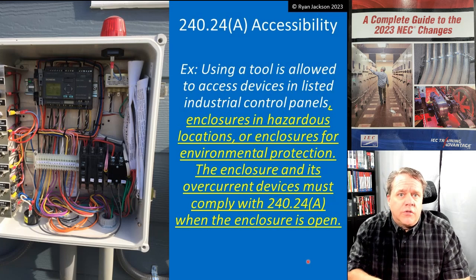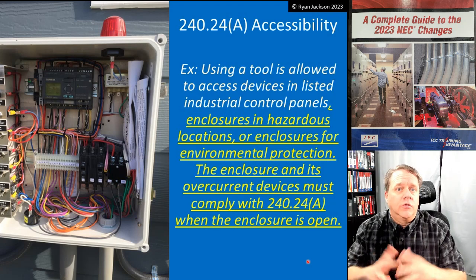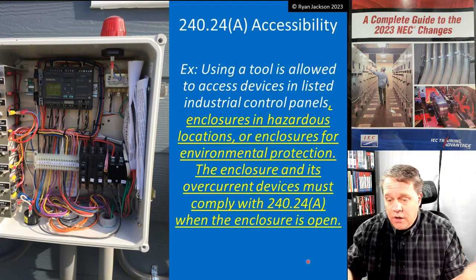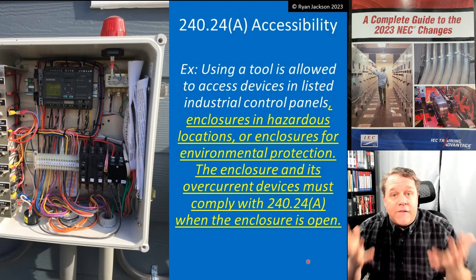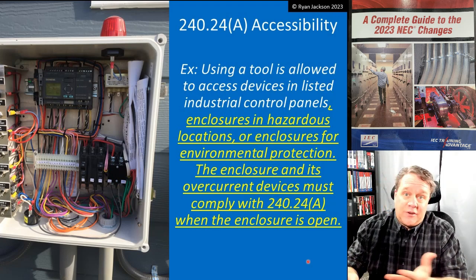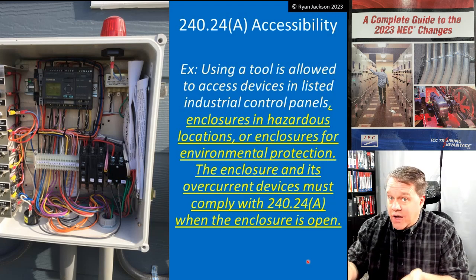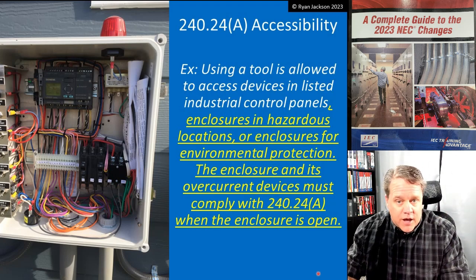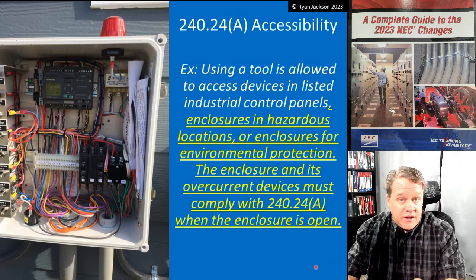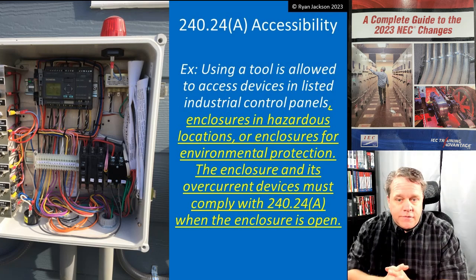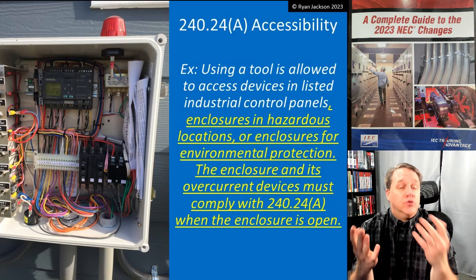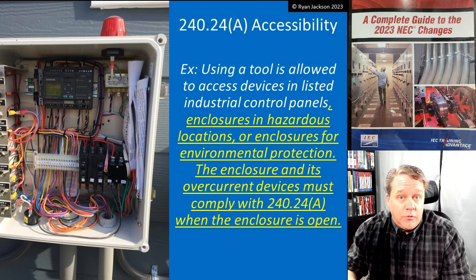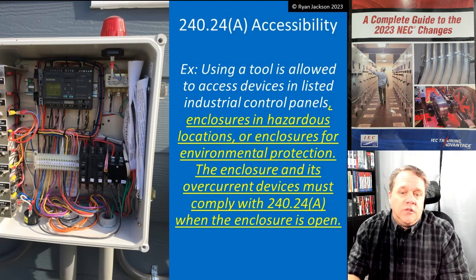Or enclosures for environmental protection — if you have a stainless steel enclosure or 3R enclosure designed for corrosion protection or hose-down protection, the circuit breaker isn't just right there; you might have to undo the cover with a screwdriver. Most inspectors were already viewing it that way, but that's not what the code said. So: using a tool is okay in listed industrial control panels, enclosures in hazardous locations, or enclosures for environmental protection. The enclosure and its overcurrent devices must comply with 240.24(A) when the enclosure is open — opening it with a tool is perfectly fine.